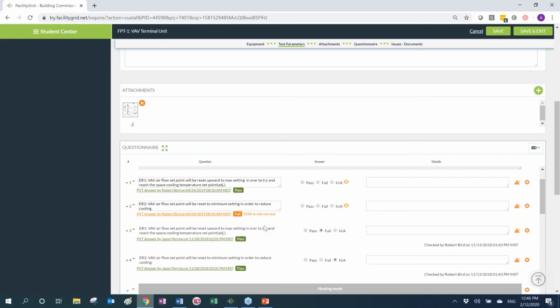Your test script may not match what's installed on site for plenty of reasons—something in the script, or the sequence of operation may have changed since you created it, or other activities may lead to something like this. The ability to pre-test equipment helps you and the contractor, because nobody wants a failed test reported. When someone pre-tests it and reports it, it doesn't appear as a failed test—it just appears as a test that needs to be reviewed before actually conducting it.